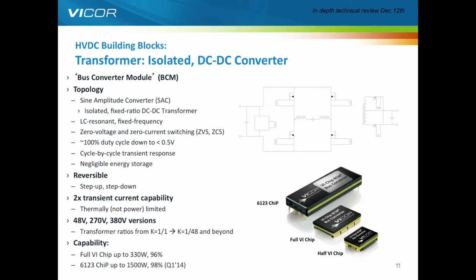Again, this is zero voltage switching and also zero current switching in all of the different cycles, which means very high frequency, in this case up to 1.7 megahertz on the primary switching frequency. This particular topology is an LC resonant, where LC refers to the tank in which charge is stored during the switching cycles. The L, the inductor, is the leakage inductance of the transformer. The C, the capacitance, are physical capacitors within the module.